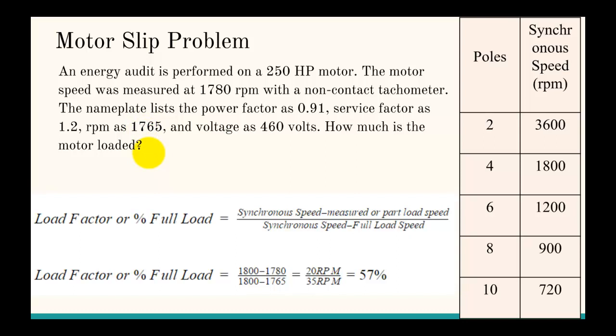Let me give a quick overview of motor slip so you get the general idea. If a motor has nothing hooked up to it, it's going to run at one of these synchronous speeds depending on the design. The design aspect is the number of poles. Basically it's going to run at one of these speeds, either 3600 RPM all the way down to 720. What happens is as you put a fan or a pump or something on the end of the motor, it's going to start slowing down a little bit. It doesn't slow down a ridiculous amount. In this case, we know that since we're close to 1800, that's the synchronous speed. You just look at the RPMs and pick the one that's above that only by a little bit. So we're not going to pick 3600, we're going to pick the one that's next above it. This table is a nice thing to have in reference when you are taking the CEM.